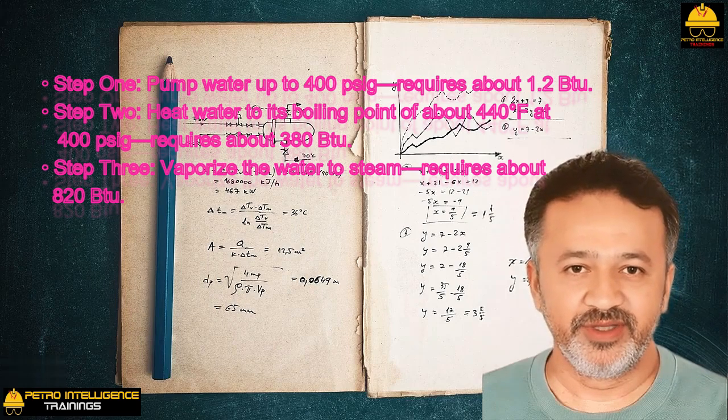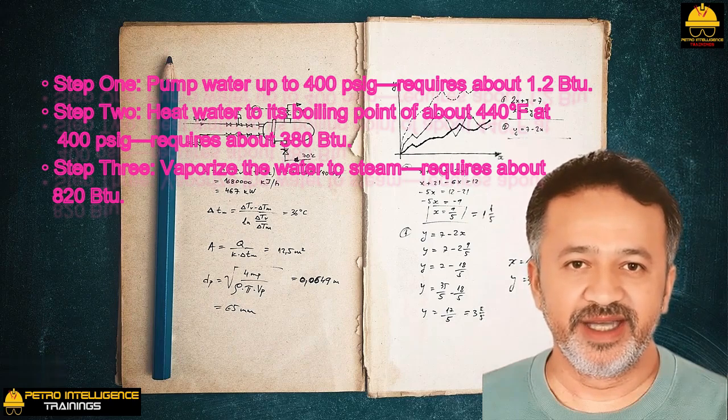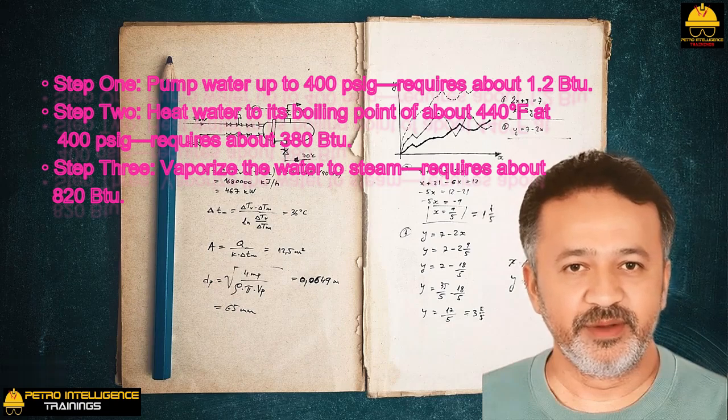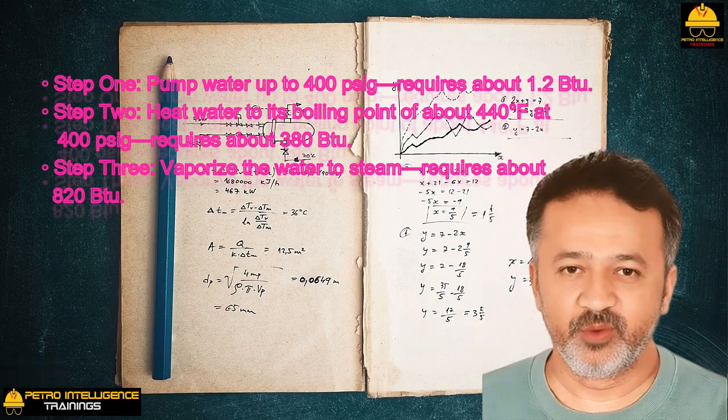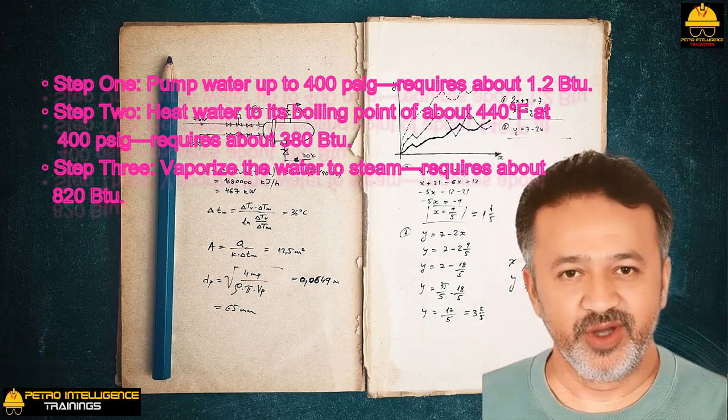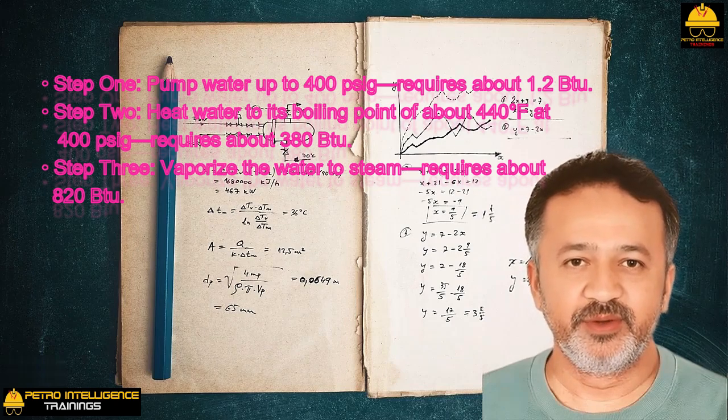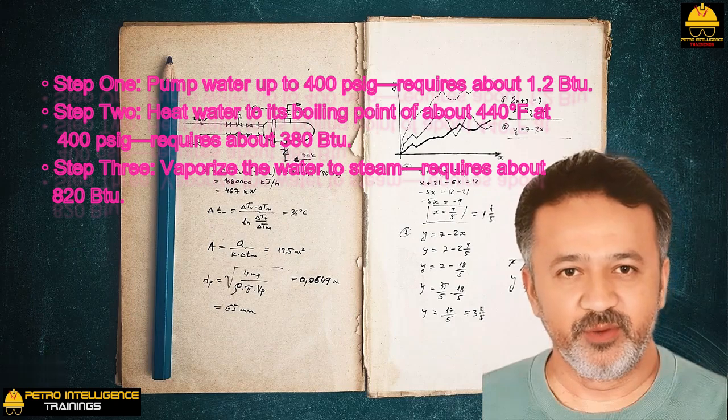Step one: pump water up to 400 psig requires about 1.2 BTU. Step two: heat water to its boiling point of about 440 degrees Fahrenheit at 400 psig requires about 380 BTU. Step three: vaporize the water to steam requires about 820 BTU. Any boiler plant operator trying to optimize steam generation efficiency will worry most about the firebox and convective section economizer, and not the boiler feed water pump.